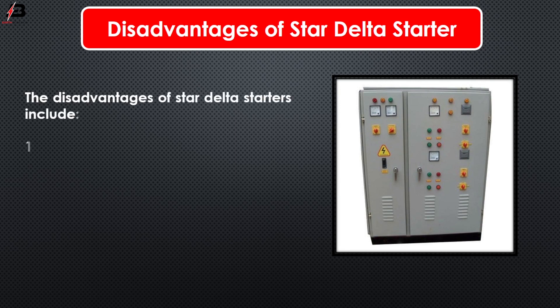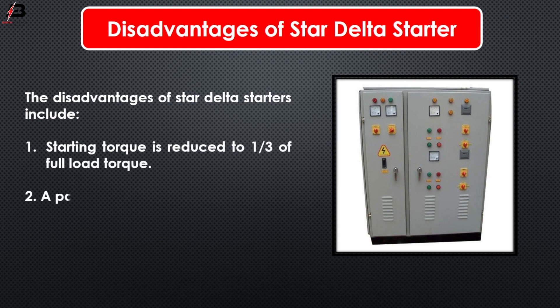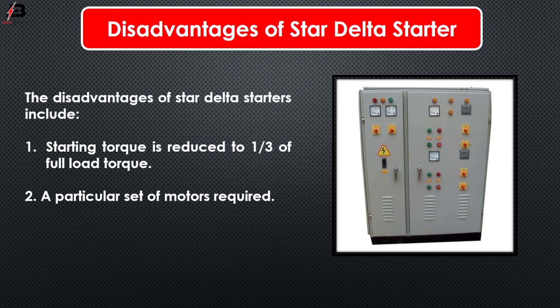Disadvantages of star delta starter: The disadvantages include: 1. Starting torque is reduced to 1/3 of full load torque. 2. A particular set of motors is required.